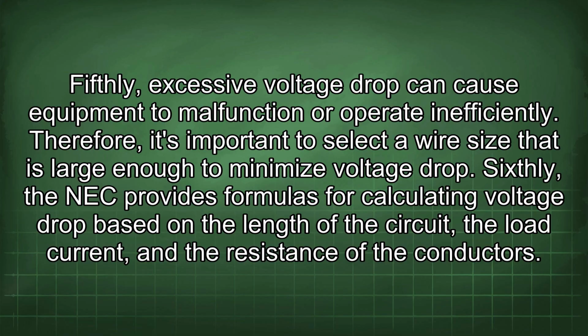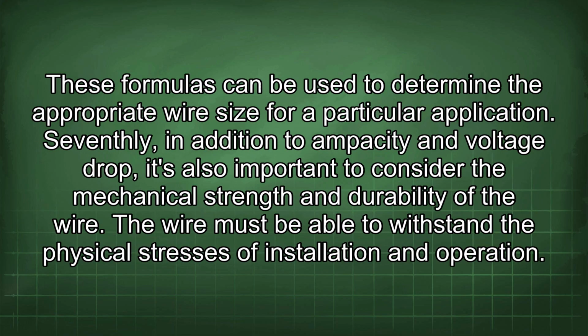Sixthly, the NEC provides formulas for calculating voltage drop based on the length of the circuit, the load current, and the resistance of the conductors. These formulas can be used to determine the appropriate wire size for a particular application. Seventhly, in addition to ampacity and voltage drop, it's also important to consider the mechanical strength and durability of the wire. The wire must be able to withstand the physical stresses of installation and operation.